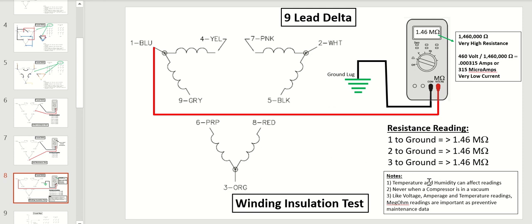Couple notes about megohm testing: temperature and humidity can affect your readings, and you should never ever do a megohm test on a compressor, a hermetic or semi-hermetic compressor, while it's in a vacuum. And just like voltage, amperage, and temperature readings that you take, megohm readings are an important reading to have for preventive maintenance data.